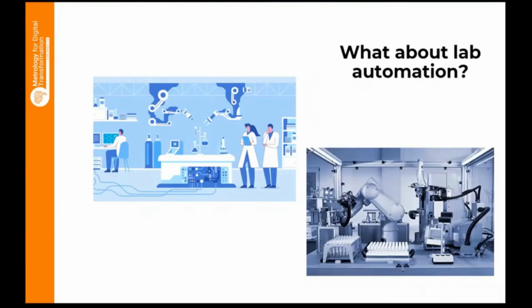We can start to generate our digital calibration certificates a step ahead of this. I mean, we can keep using our current ways of generating calibration certificates, but thinking in a digitalized form. I mean, XML format or the format that was selected by the laboratory. It's useful, but it's not necessary.